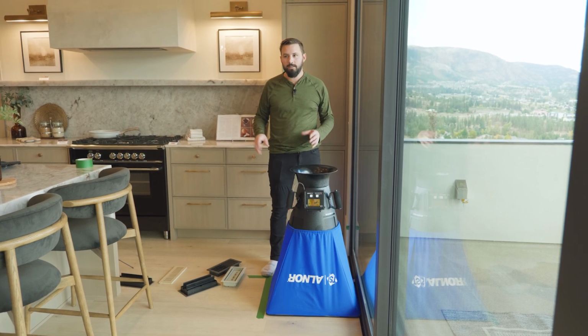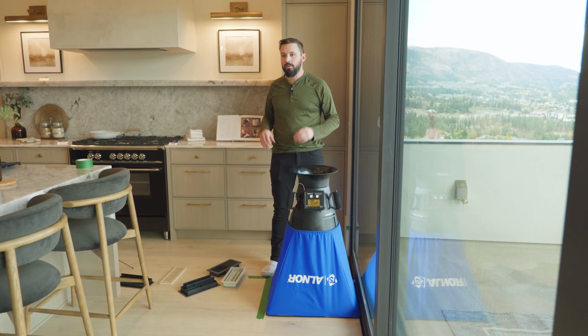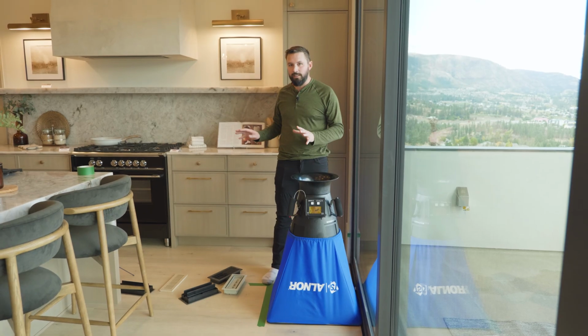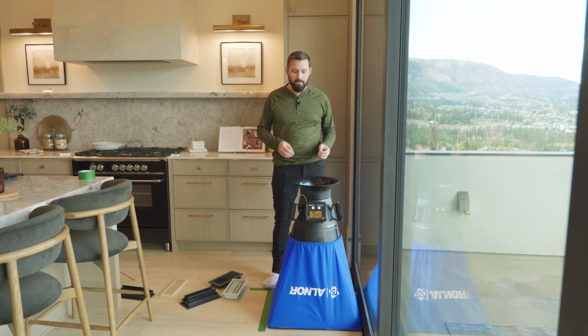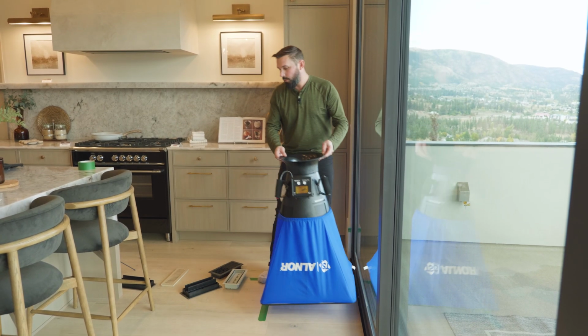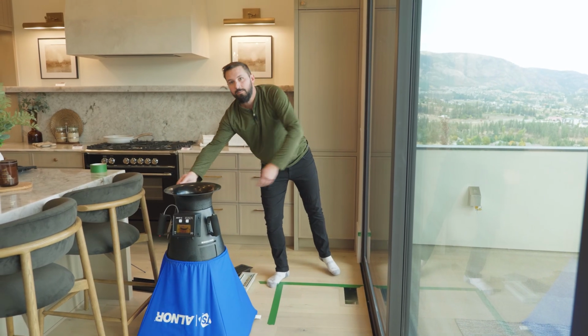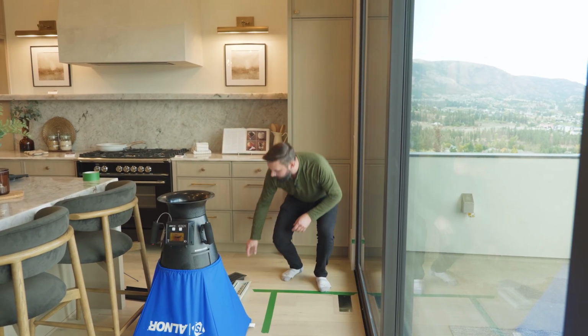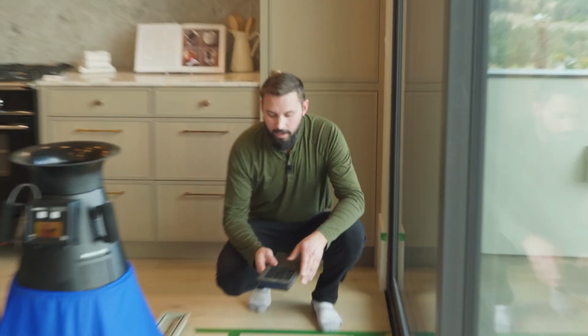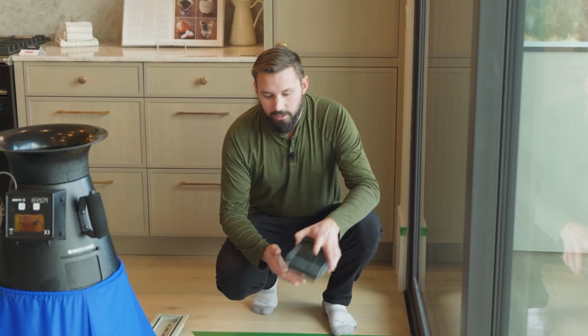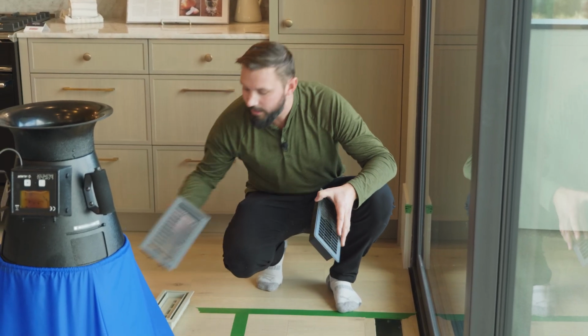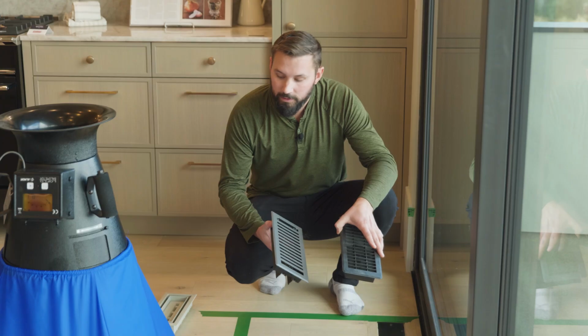We've already done a duct design. We already have a heat load calculation. We know how much air we have to put into each area, so then we commission the system. And this is where it becomes very important that we've engaged with our design team and we've talked about vent covers at the very beginning of the process. Most systems are designed to use a vent cover like this, or a vent cover like this that has a certain amount of free grill area.